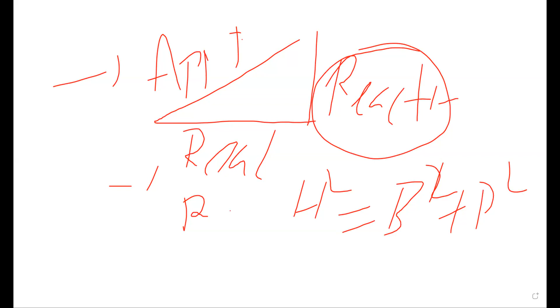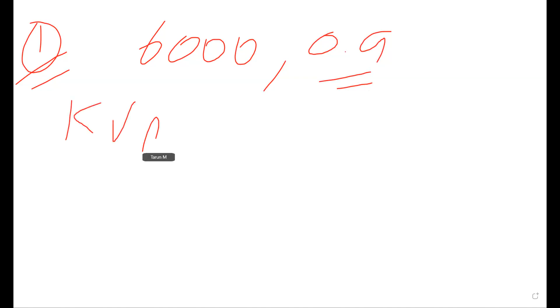Okay, till now we were talking about total power, everything related to total. Now take generator number one, which is generating 6,000 kilowatt with power factor 0.9. Can you calculate kVA in the same manner? kW divided by cos phi. What is kW now? 6,000. What is cos phi? 0.9. What will be the kVA value for generator number one?